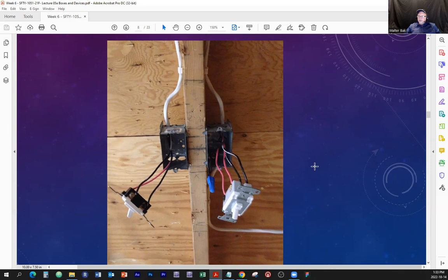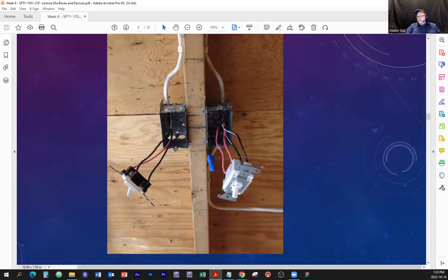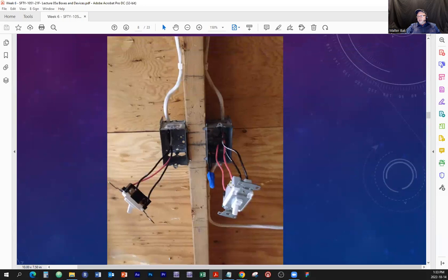So with the same size of the box, you can fit fewer wires when you're using this four-way switch than if you use that one there. And you have to look at the box, where it says whatever the volume is. According to electrical code, which you're going to study in more depth, you're going to be able to tell how many wires you are legally allowed to fit with this device in the same box. I'm raising your awareness to this.